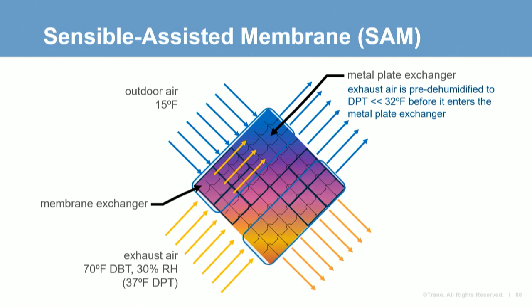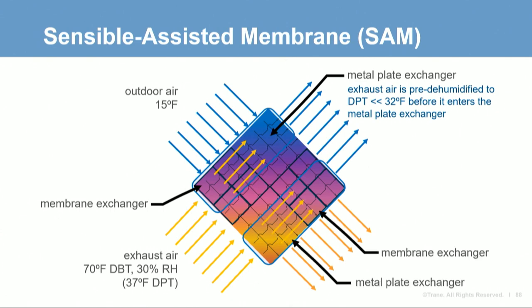Recall that the SAM exchanger uses a combination of membrane and metal plate exchangers. On the left-hand edge where the coldest outdoor air enters, the exhaust air passes through the membrane first, dehumidifying it below the 32-degree frost point before it enters the metal plate in the cold corner — removing the risk of liquid condensate turning to ice. At the far right-hand corner, icing conditions are also reduced because the exhaust air passes through a plate exchanger first where it is pre-cooled, increasing relative humidity and thus increasing the latent effectiveness of the membrane.